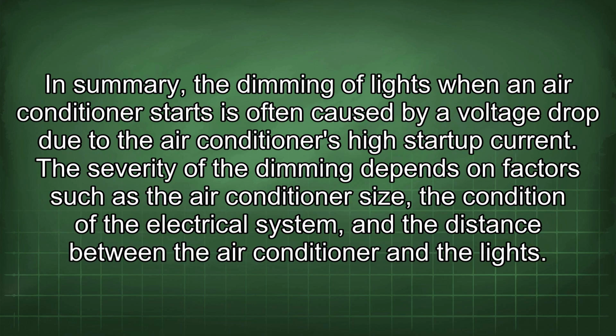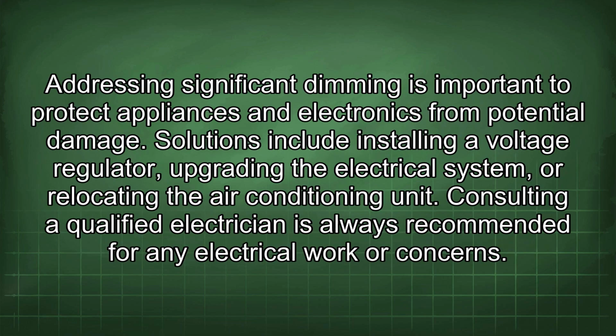In summary, the dimming of lights when an air conditioner starts is often caused by a voltage drop due to the air conditioner's high startup current. The severity of the dimming depends on factors such as the air conditioner size, the condition of the electrical system, and the distance between the air conditioner and the lights. Addressing significant dimming is important to protect appliances and electronics from potential damage. Solutions include installing a voltage regulator, upgrading the electrical system, or relocating the air conditioning unit.